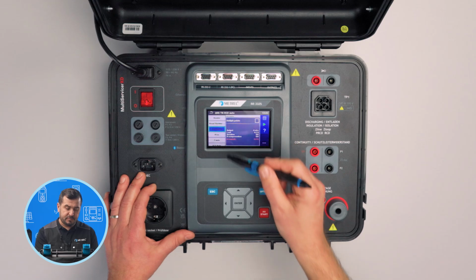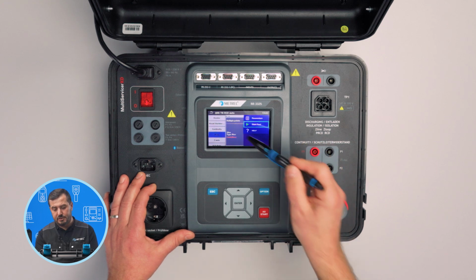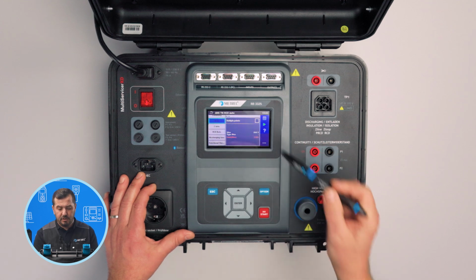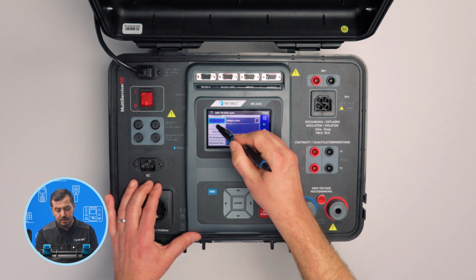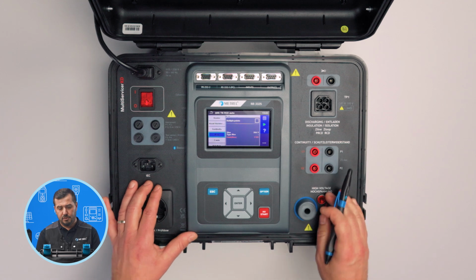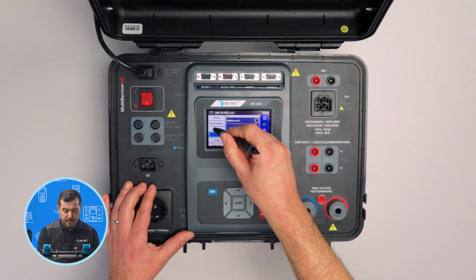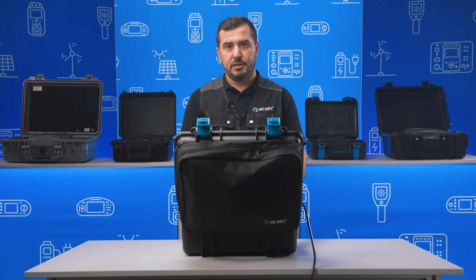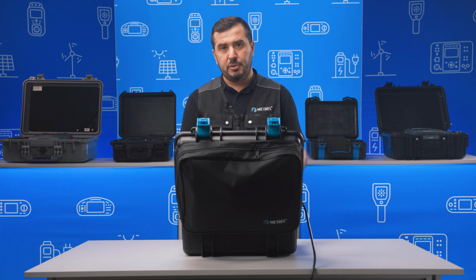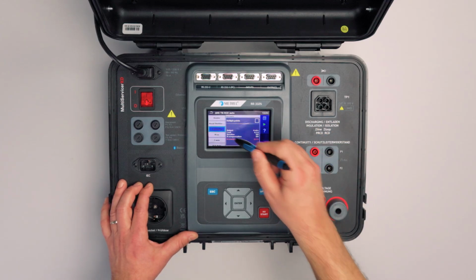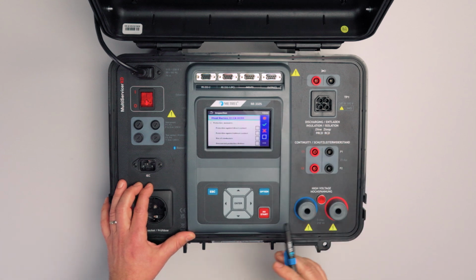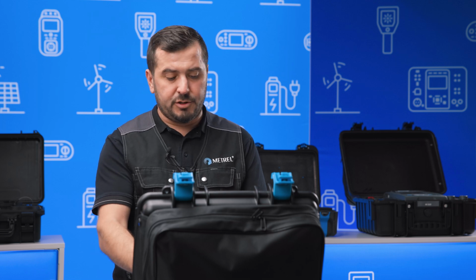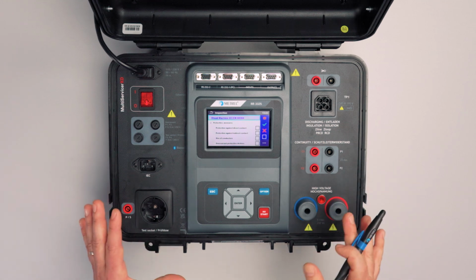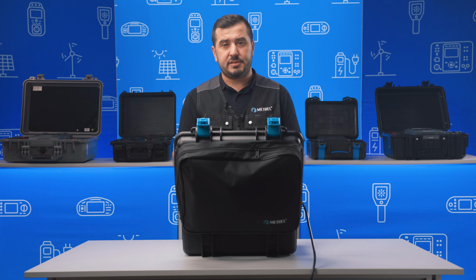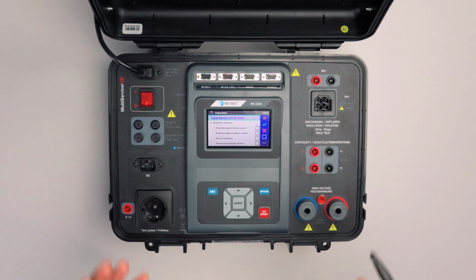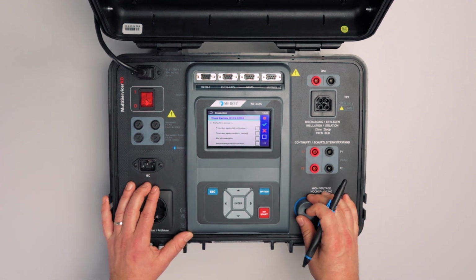So now on these particular steps, we can see that we can change parameters before we start the test. And of course, if the testing step in particular also enables multiple points, we can also choose multiple points for this specific testing step. If we say, for example, earth continuity, and we choose multiple points, this means that the instrument during this auto sequence will repeat this step until the loop is finished. So that's basically it about the parameters, and we can simply start the test here. So after the test sequence is started, the user has the option to go through all these procedures. The auto sequence can have built-in pictures, built-in texts, built-in pauses. So a lot of options during the auto sequence, but all of this must be made on the PC software side.